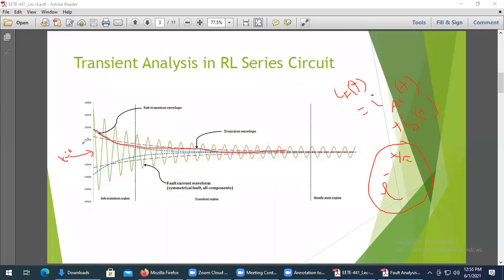So at the very beginning of the fault, if you consider this as the zero line, the DC component is maximum. The AC part is always additive to the DC component, so since the DC component value is maximum or very high, the total fault current will be very high at the very beginning of the fault.